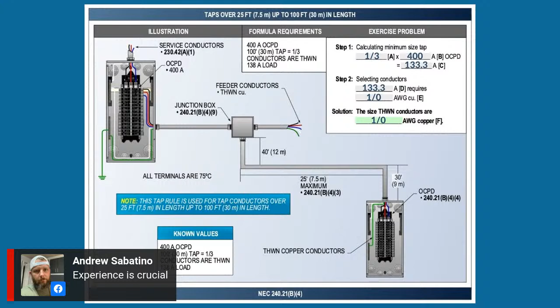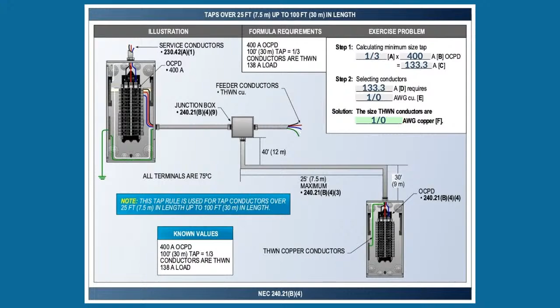There's not. Now, if I look at this, it's 25 foot up to 100 foot. I've got a 400 amp overcurrent device upstream. I take it at a third. That's 133.3 amps. The next size above, that's 150 amps. We're doing copper conductors here, and that would be a 1-aught conductor. That's how simple it is. Right. So basically, you don't have a 140 amp overcurrent device, so you would go up to a 150 amp overcurrent device in this case.